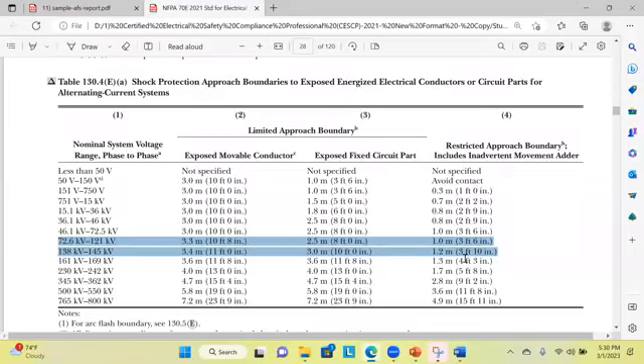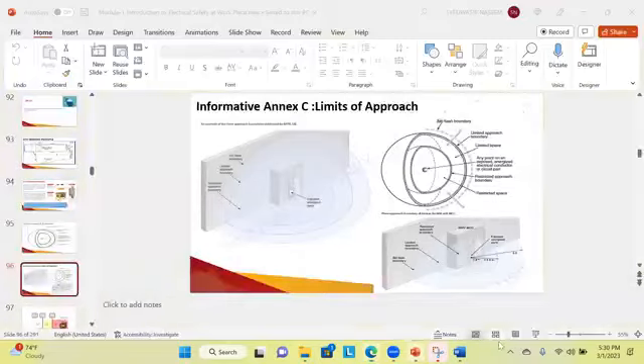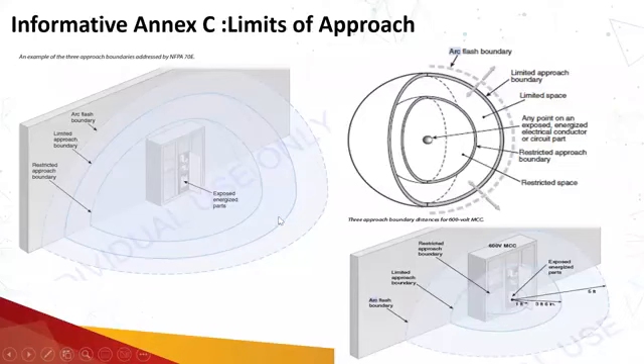So why is it like this, that the limited approach boundary is one thing and the restricted approach boundary is defined as another? From here the question arises: what does each boundary trigger? We have to keep in mind that the limited approach boundary is the triggering point for unqualified persons. You have to keep unqualified people away from those energized circuits and conductor parts by a minimum of the limited approach boundary. They are not allowed to enter the limited approach boundary unless they are escorted by a qualified person. Otherwise, they are not allowed.